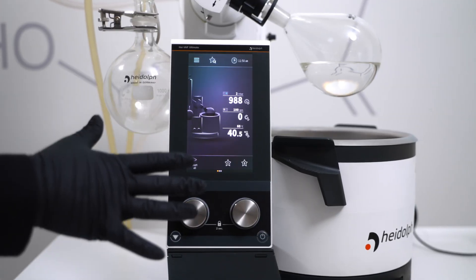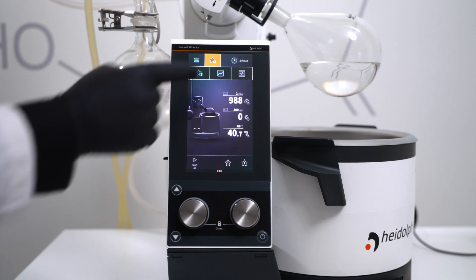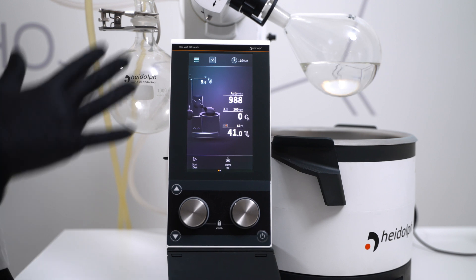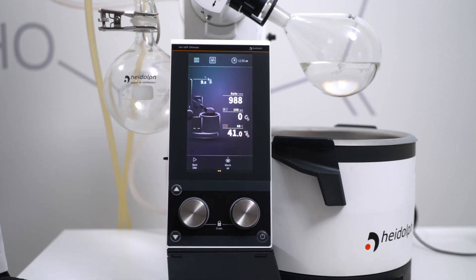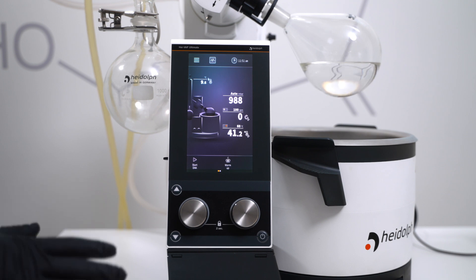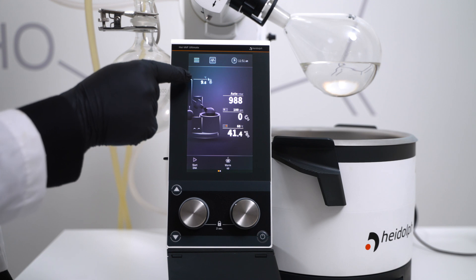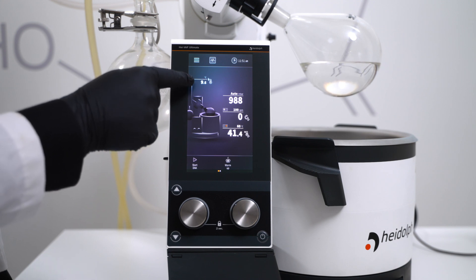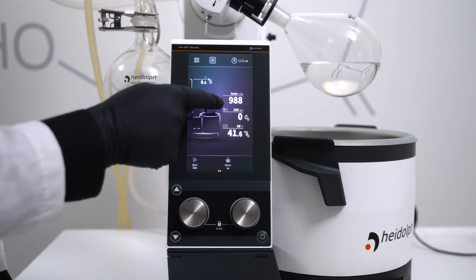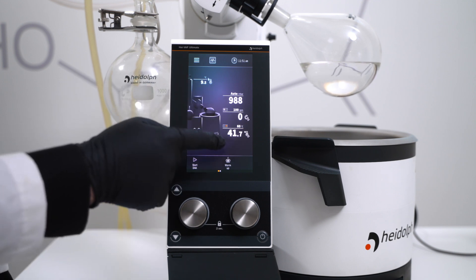Starting from your normal screen, to get into DAA, we're going to first touch on the star at the top. From there, DAA is the third option, and you're going to come to a screen like this. What we see is somewhat similar to your standard manual evaporation specs, but with a few differences. The first being that you can see the temperature of that DAA temperature sensor. You see that you cannot adjust your vacuum level — it has been set to auto. But besides that, we can set our rotation speed and our heating bath speed.